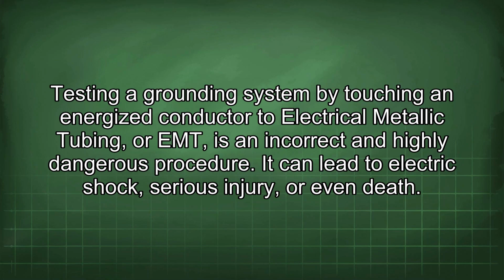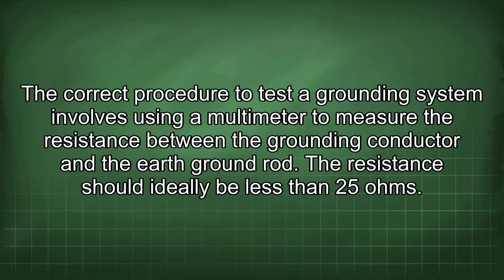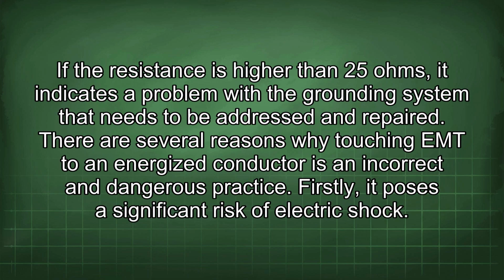Testing a grounding system by touching an energized conductor to electrical metallic tubing, or EMT, is an incorrect and highly dangerous procedure. It can lead to electric shock, serious injury, or even death. The correct procedure to test a grounding system involves using a multimeter to measure the resistance between the grounding conductor and the earth ground rod. The resistance should ideally be less than 25 ohms.